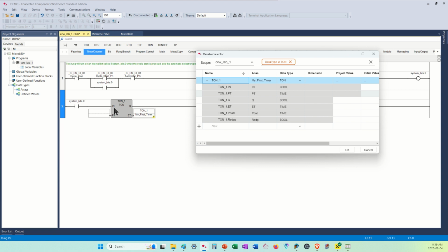So in this case, we're conditioning it so the timer doesn't run 24/7. We just literally have an input, and whatever logic is ahead of it must be true. So that will start the whole process. Then we have this Q on the other side, on the right-hand side, and it's connected directly to our run. So that Q energizes when the timer has done its job.